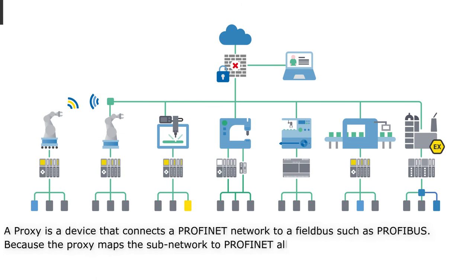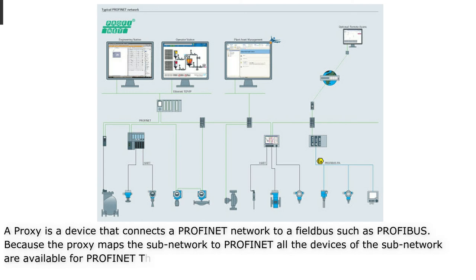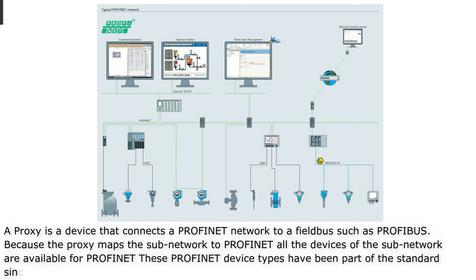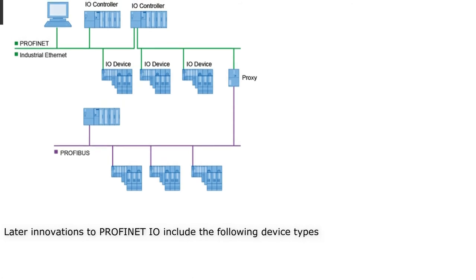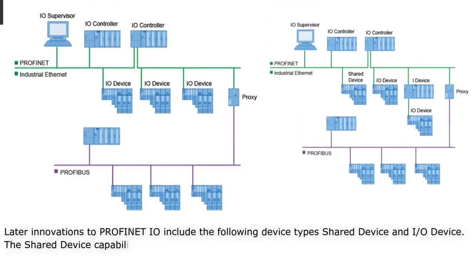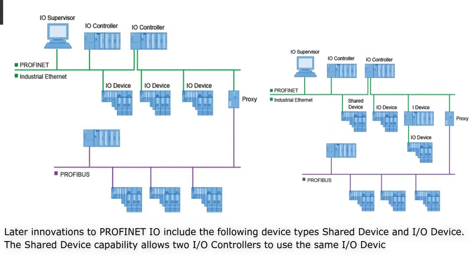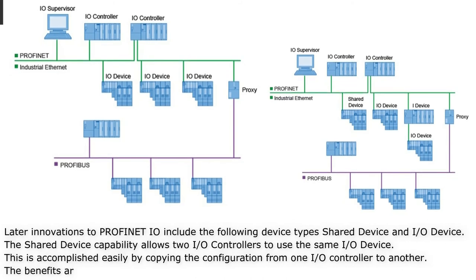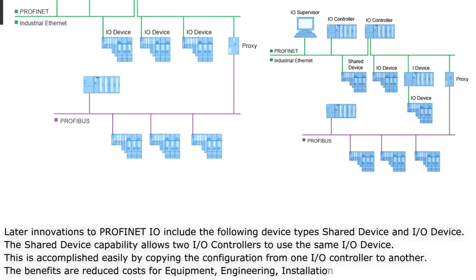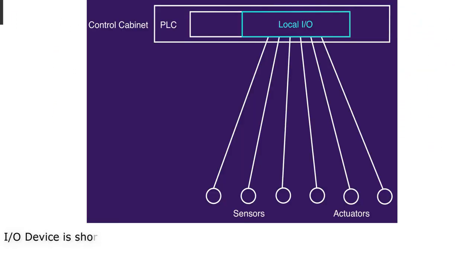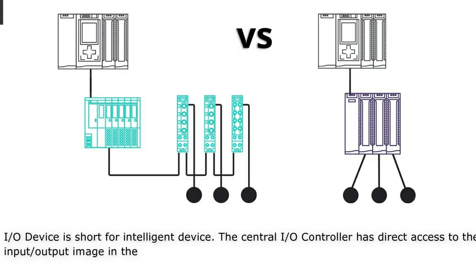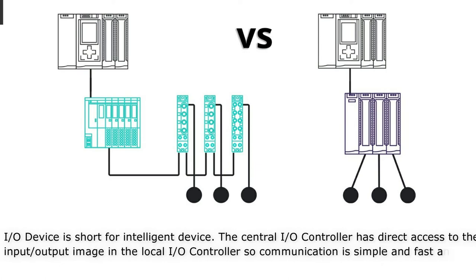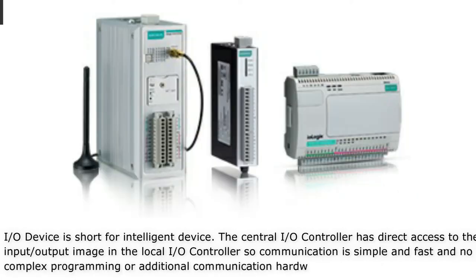Because the proxy maps the sub-network to Profinet, all devices of the sub-network are available on Profinet. Later innovations to Profinet I-O include the shared device and I-Device types. The shared device capability allows two I-O controllers to use the same I-O device, accomplished by copying the configuration from one I-O controller to another, reducing costs for equipment, engineering, installation, and maintenance. I-Device (intelligent device) allows the central I-O controller direct access to the input/output image in the local I-O controller, so communication is simple and fast with no complex programming or additional communication hardware required.